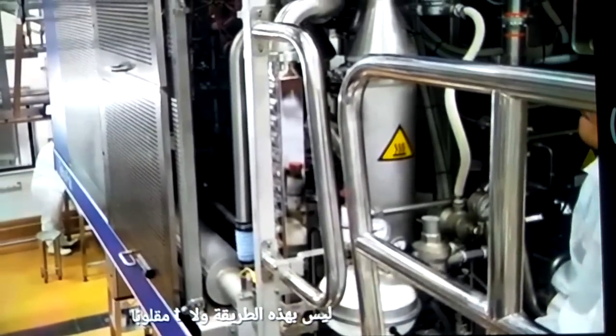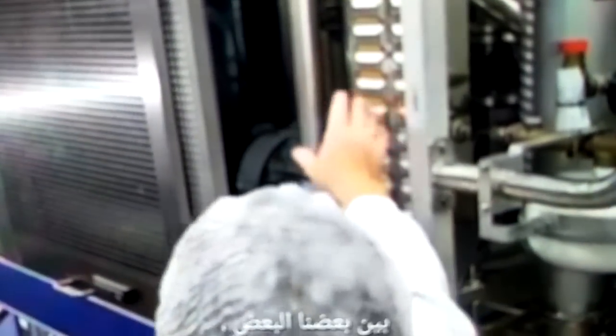And not upside down. Valve. This is just a cover. Okay? It's just a cover for the heat exchanger. So you can see cracks appearing here. It happens because the heat exchanger is heating and cooling itself. This bit on the end is just a cover. So it's got cracks here, somewhere there. So this you have to remove at certain hours. Put it in a water bath, half a bar pressure, regulated air, check, make sure you have no leakage between one and another.